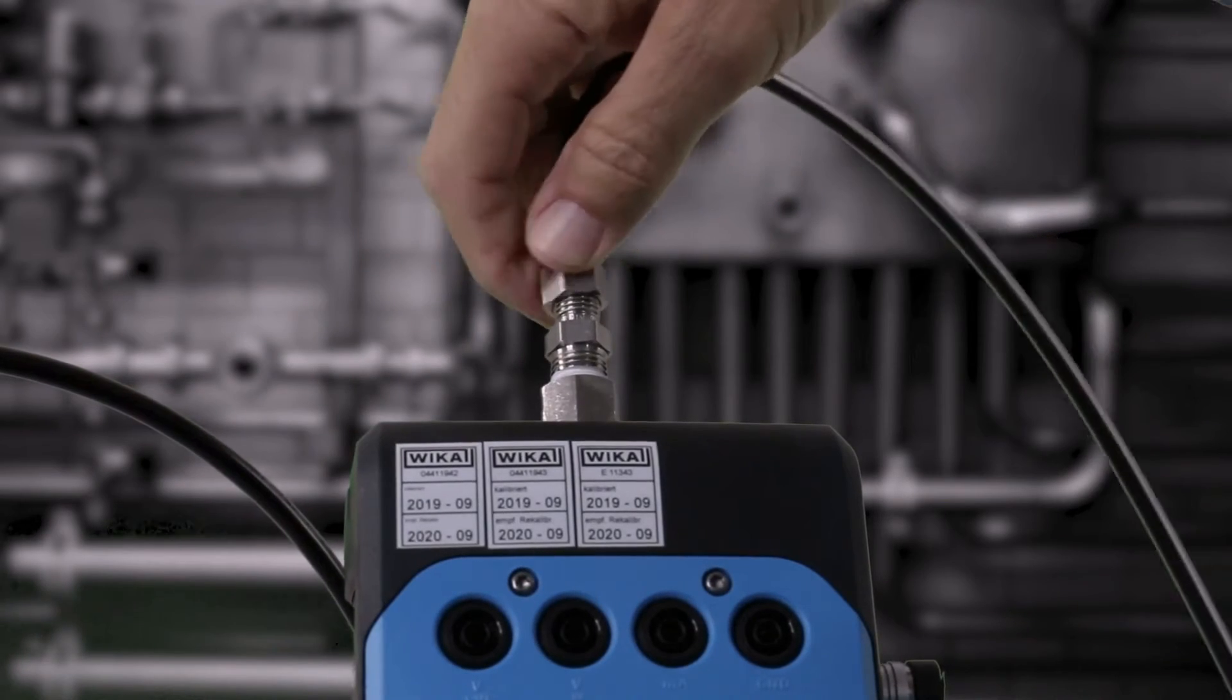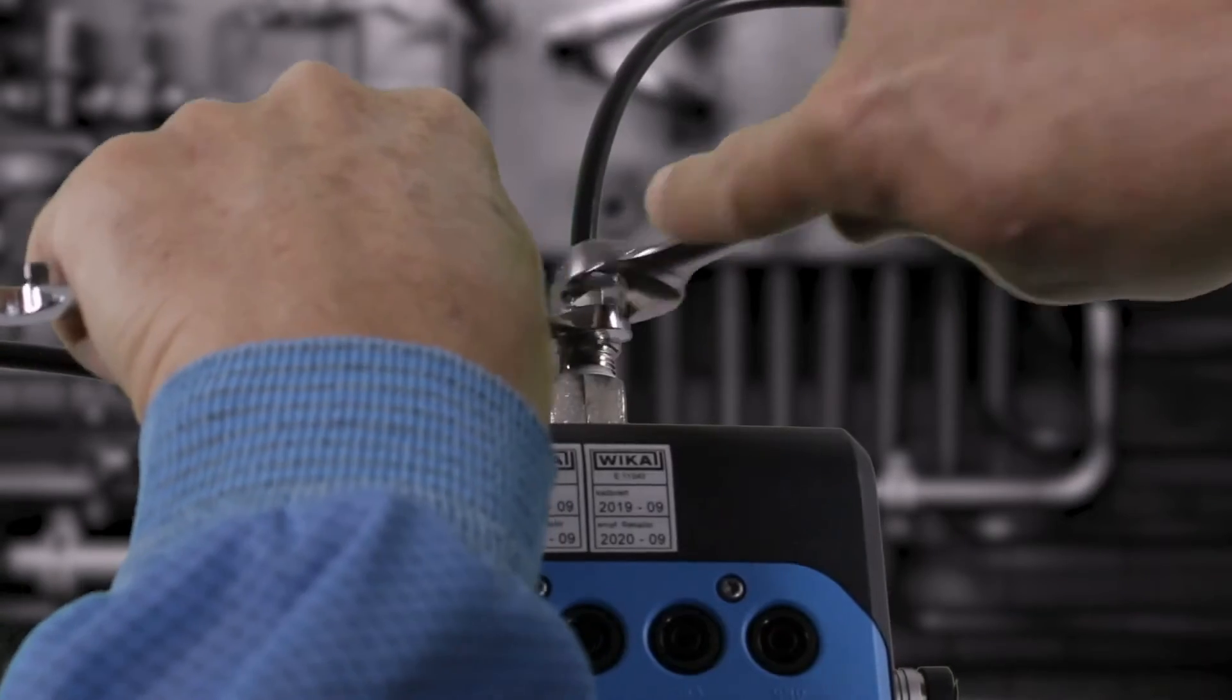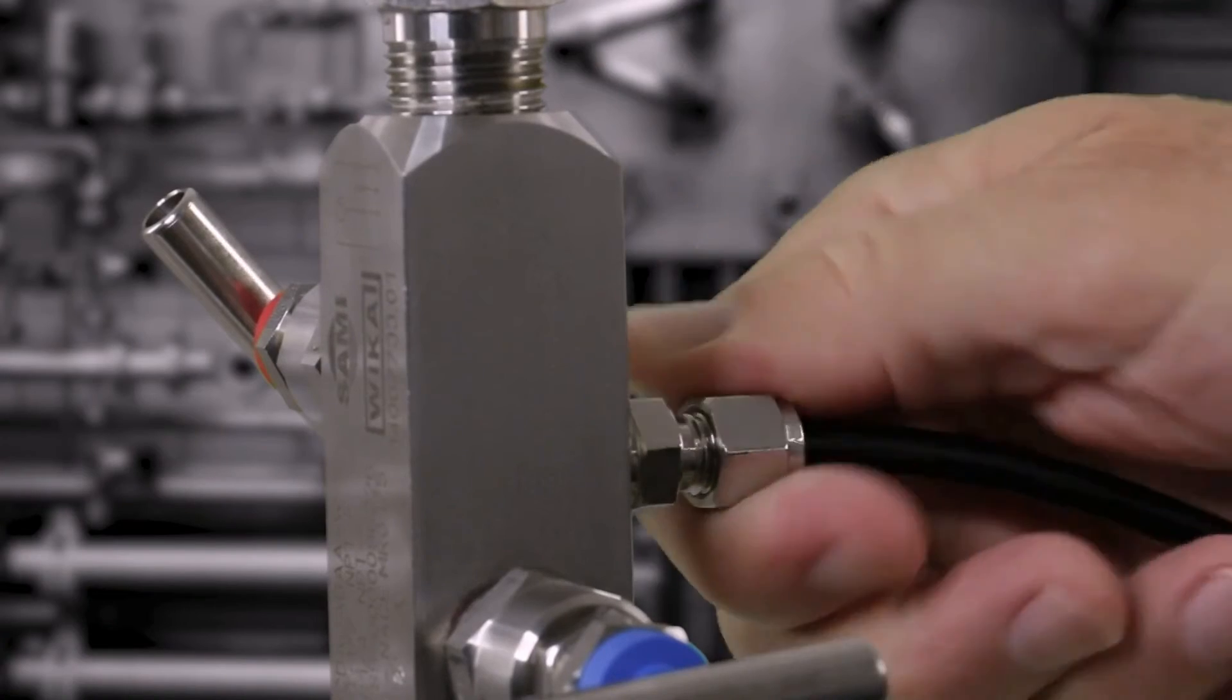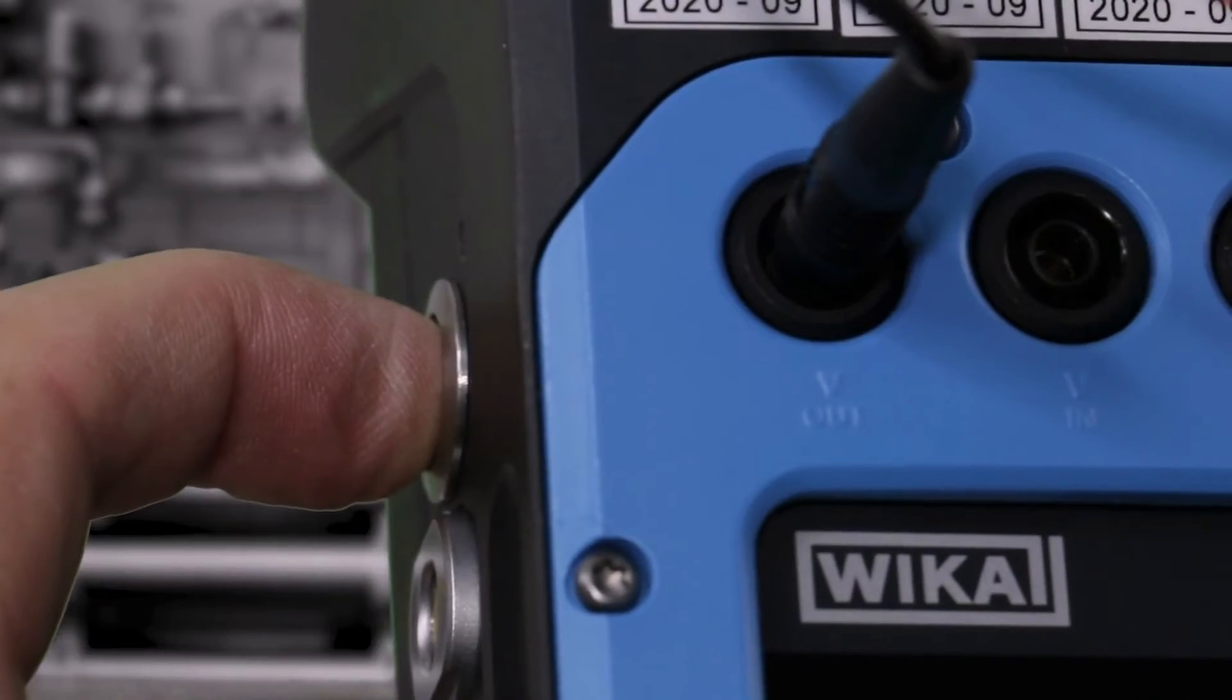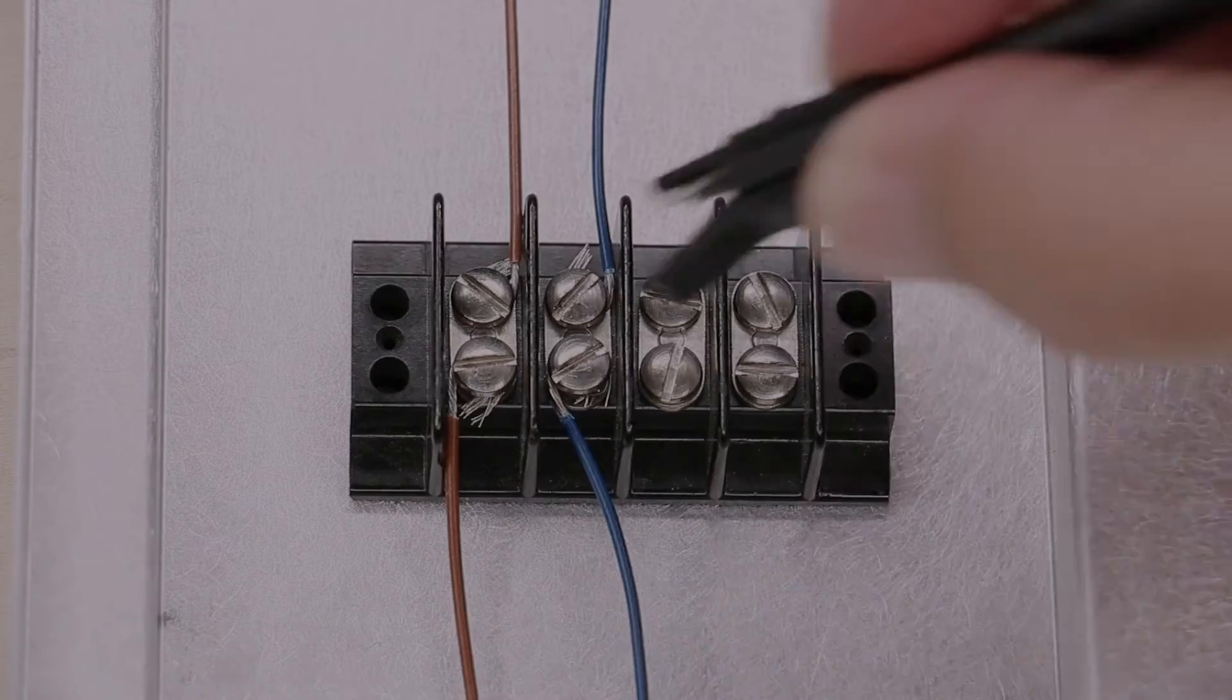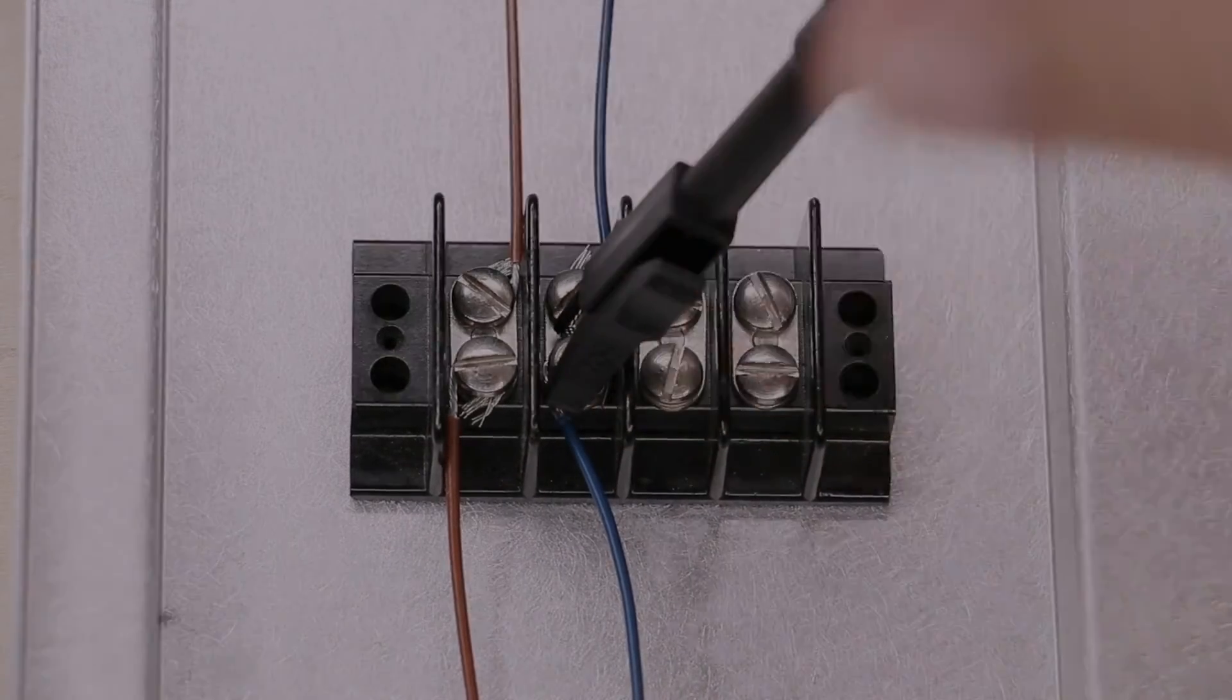Connect pressure rated tubing to the CPH7000X calibrator. Connect the other end of the tubing to the test port on the block and bleed valve. Turn on the CPH7000X. Connect the calibrator test leads to the terminals and to the calibrator.